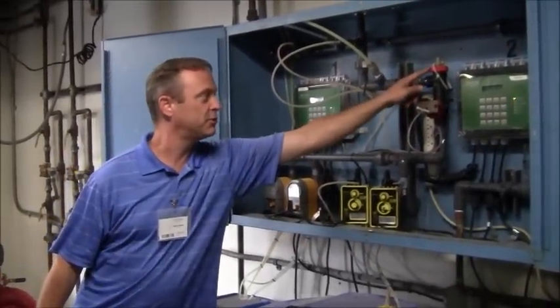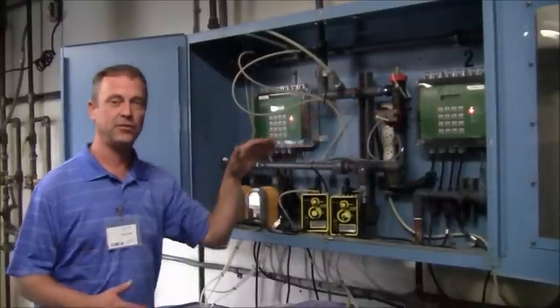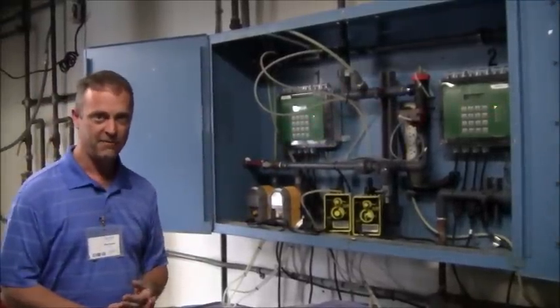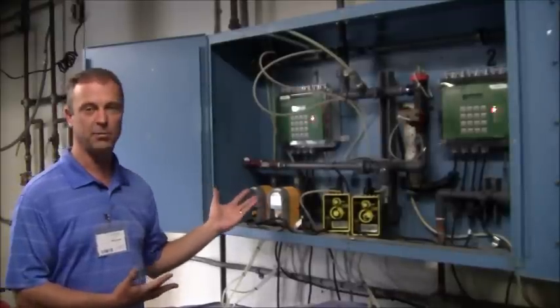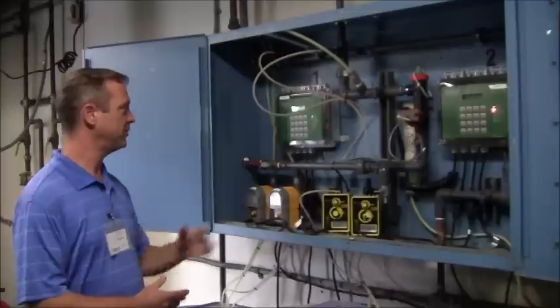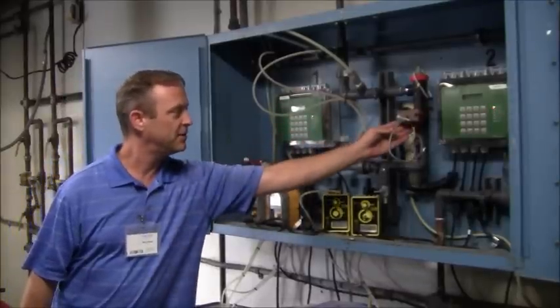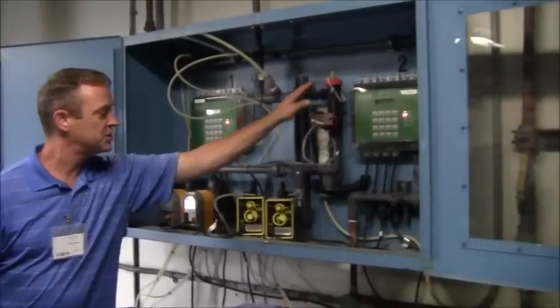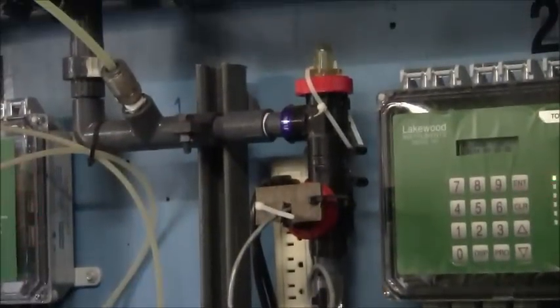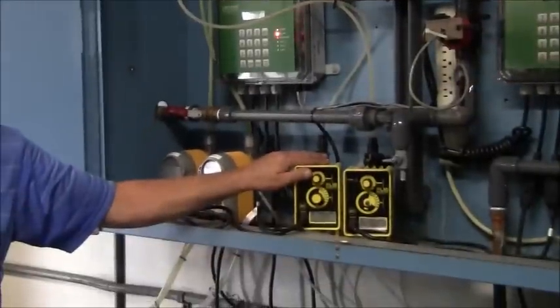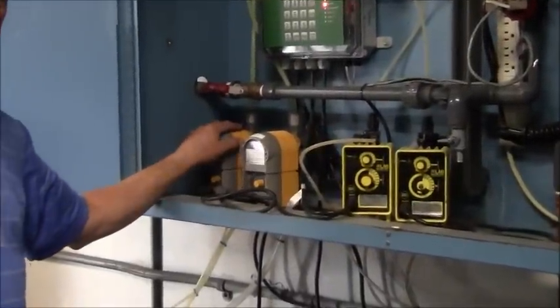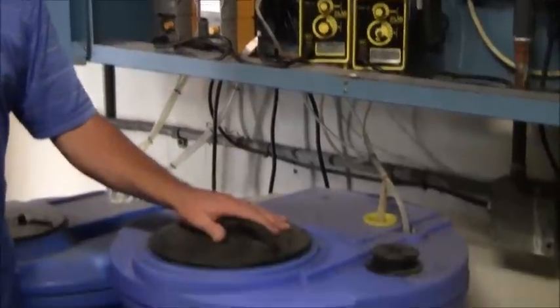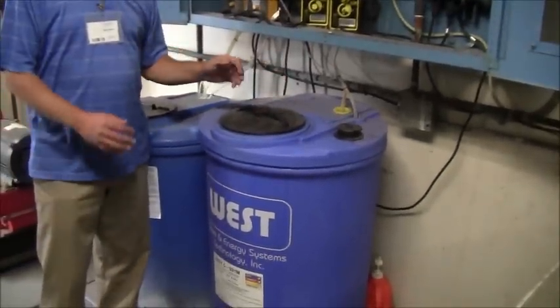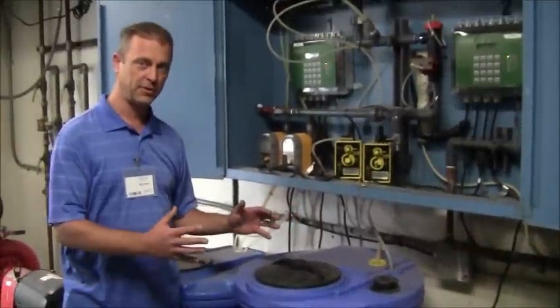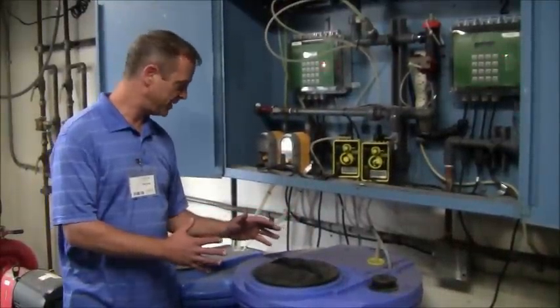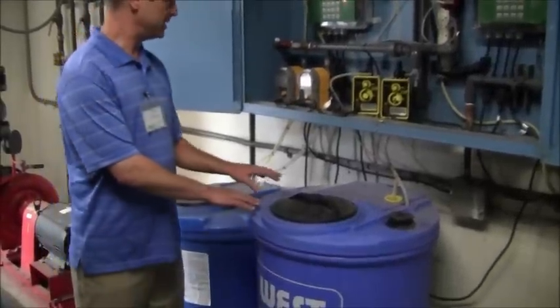system. And that's because this flow switch is designed to protect the system when we don't have flow, so we're not feeding chemical into a stagnant line and just wasting product. So once again, we try to be efficient. So the typical controller will come with a conductivity housing probe, a flow switch, and then your sample stream back. And we're feeding an inhibitor through this chemical pump and a biocide through this chemical pump. And then you have a double-walled feed tank for safety. So every plant would want to see this. If your fire marshal comes up here, he wants to see the chemicals are double contained and housed properly. And then this is your biocide containment here.